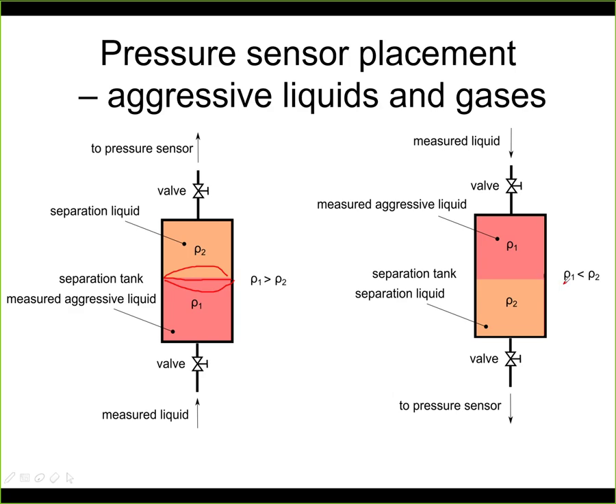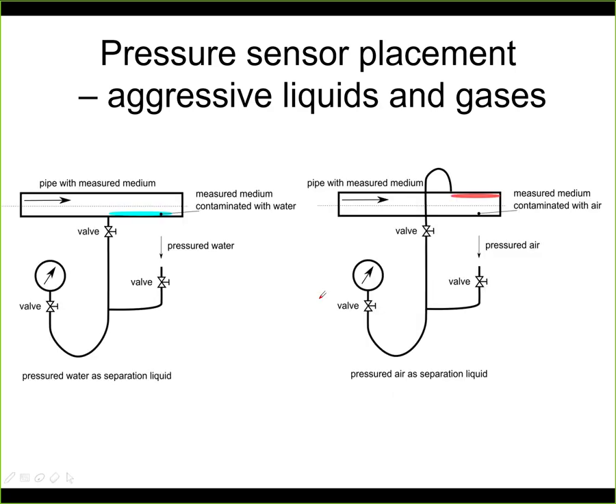Now in the second case, as you see here on the right, the separation liquid actually has a higher density than the aggressive liquid, and therefore this pressure gauge is installed on the bottom and the measured liquid is on the top. Now if this assumption is not valid, if for example the densities change so that it may be for one temperature this case and for another temperature this case, then you need to use the diaphragm as I've shown you here in this example. Now the most common separation liquids are water, oil and air. So let's take a look on how to use water or air as a separation liquid.